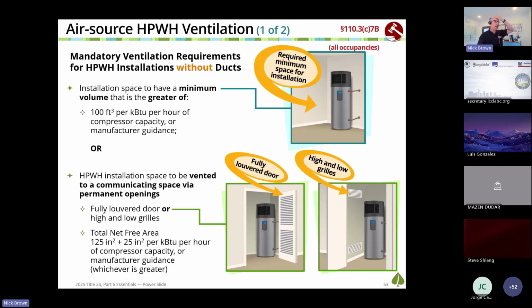Here's a big one I like to highlight in all my classes. Heat pump water heaters are becoming more common in single family and multifamily buildings. What's different about them is they pull the heat that they put in the water from the space around them. So it's really important to consider the location we choose and the airflow or air supply. So we've got new mandatory ventilation requirements for heat pump water heaters that cover all occupancies, non-res, single family, and multifamily in section 110. And here are the choices.